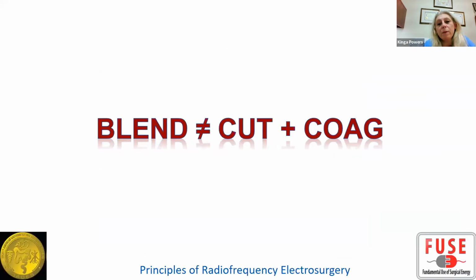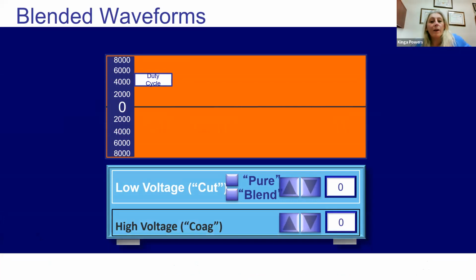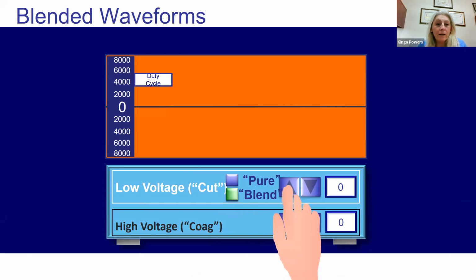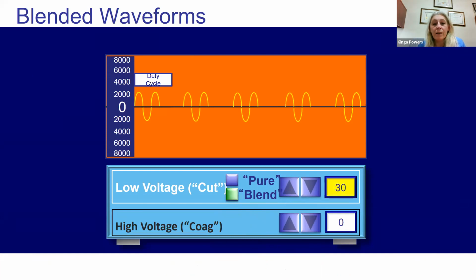So what is the blend waveform? Many people think that it has to do with combining the cut and coag, but that's actually a misnomer. It has to do with the duty cycle. The coag can actually be set at zero and it's the same. In the blend waveform, you can use a low voltage or higher voltage, depending on what you set it on. But basically, you set the percentage of the time that the current comes out of your ESU. So you can have it here at 50%, and the voltage is a little bit higher than if you had it on pure cut, but it's definitely lower than with the coag mode. So this is a 50% duty cycle in the blend mode.